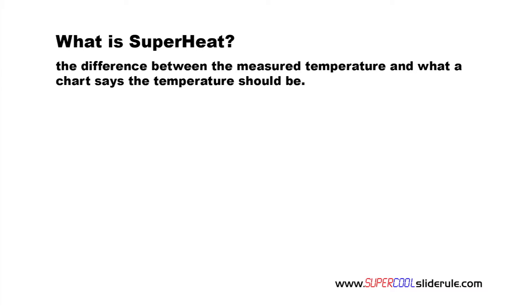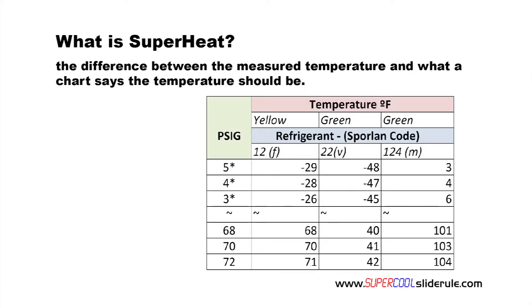Here is an example. If we reference a temperature pressure chart for R22, we will note that at 70 PSI our temperature should be 41 degrees.